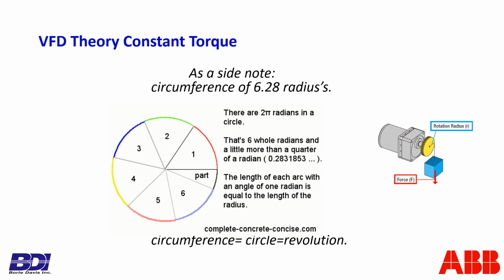Here we have a circle, and in this circle, this is the same as a revolution of the motor. And the pulley on the motor has a radius. And the radius, if we laid it on the circumference over and over and over and over until we made one complete revolution, we would note there are 6.28 radiuses that can be laid out to make one revolution or to make one circumference of the motor. That's what that means. That's where that 6.28 comes from.